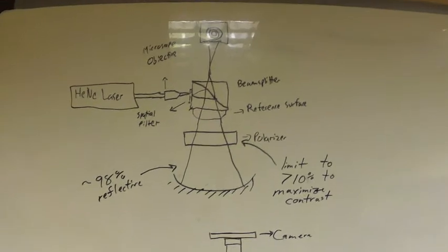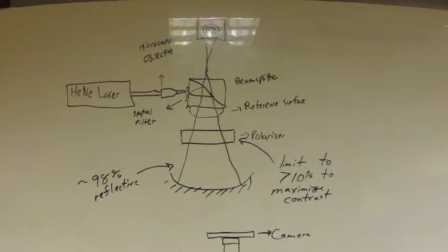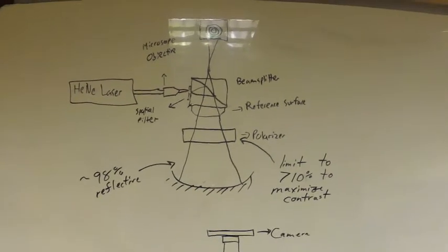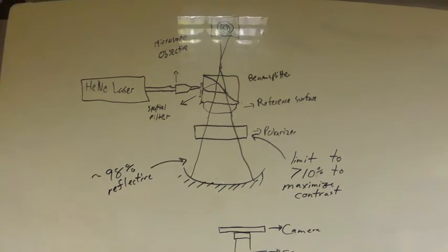In this lab, we use a Shack cube interferometer, which is conceptually similar to the shear plate interferometer, with the only difference being that the shear plate interferometer interferes a wavefront with itself, whereas the Shack cube interferometer interferes an aberrated wavefront with a nearly perfect one.